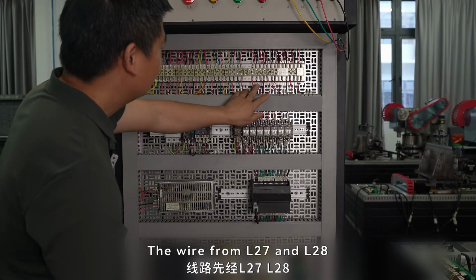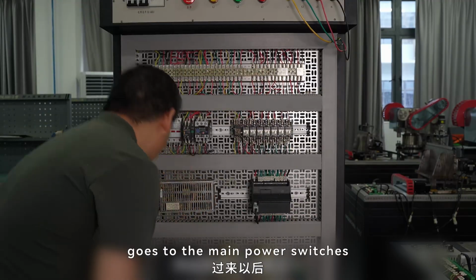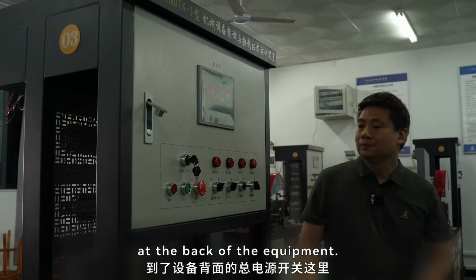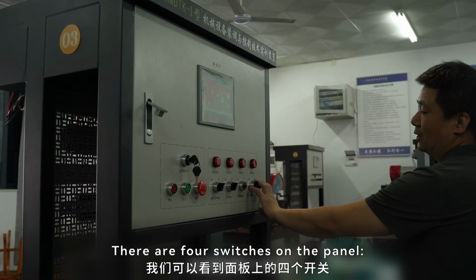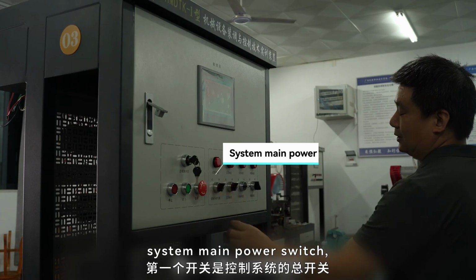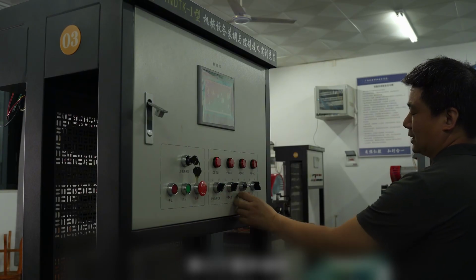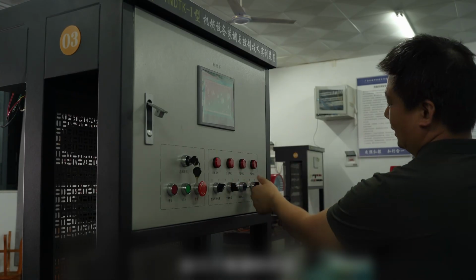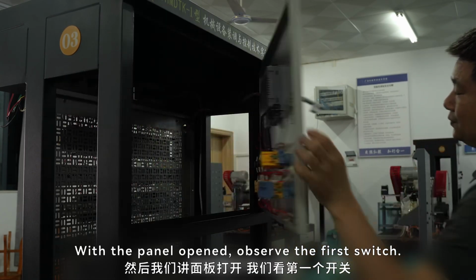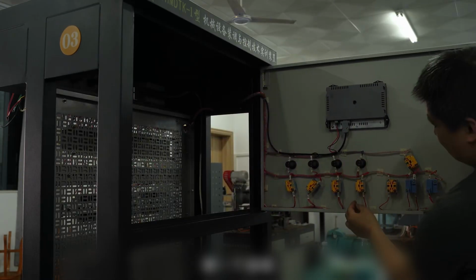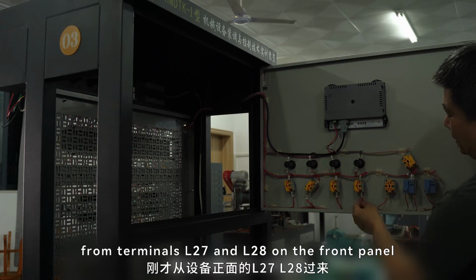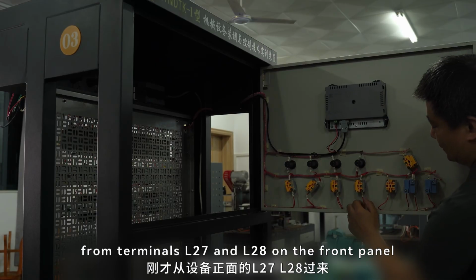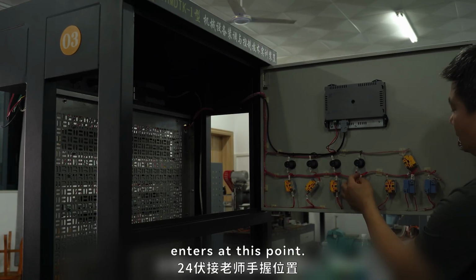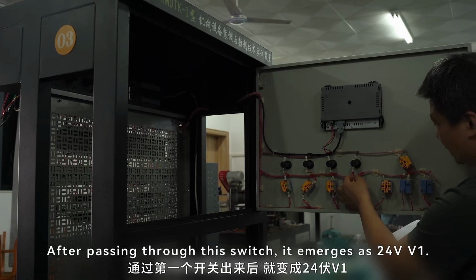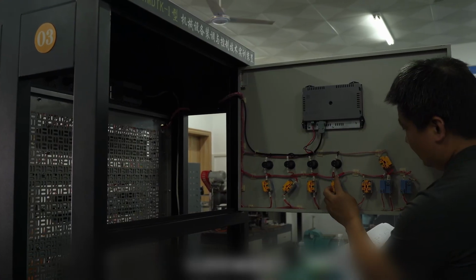The wire from L27 and L28 goes to the main power switches at the back of the equipment. There are 4 switches on the panel: system main power switch, AC motor power switch, stepper motor power switch, and servo motor power switch. With the panel opened, observe the first switch. The 24 volts supply from terminals L27 and L28 on the front panel enters at this point. After passing through the switch, it emerges as 24 volts V1.